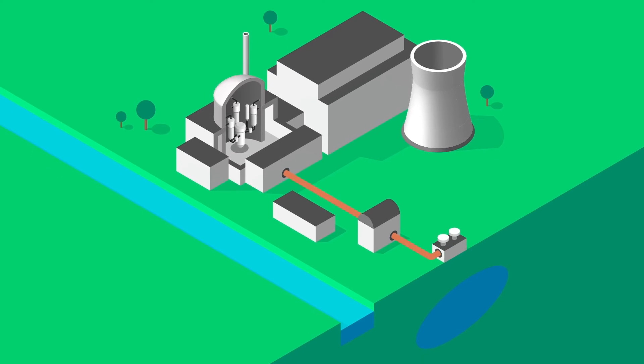In France, the material parts of this hard core are being deployed on nuclear reactors, notably during the fourth safety periodic review of the 900 megawatt reactors. These include, among other things, for each reactor: an ultimate emergency diesel generator as a backup power supply for safety systems, an on-site crisis management building sheltering the equipment needed to manage the accident as well as 100 people, and an ultimate water makeup system sufficient for 72 hours.